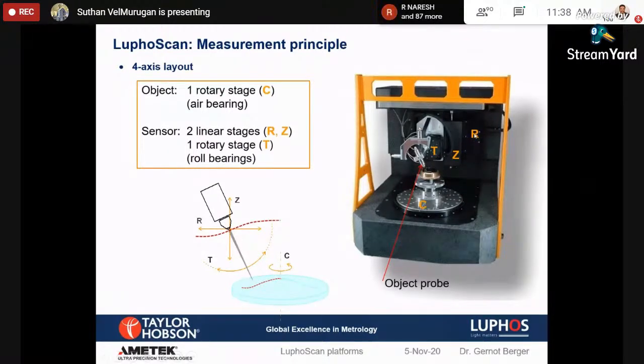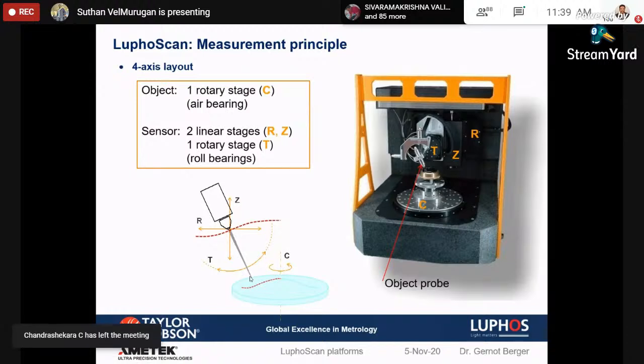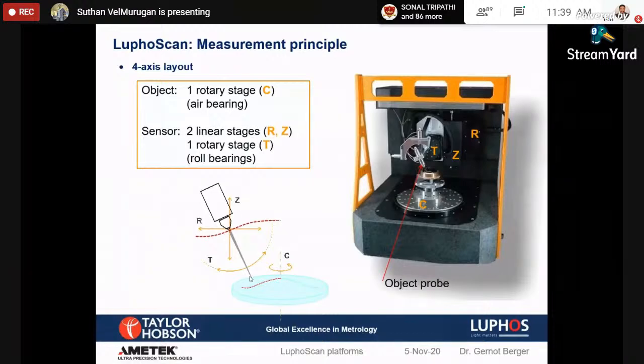The R is the arm axis, like an X-axis movement, and Z is the up and down movement. The T is the swiveling of the probe. The concept here is that the probe is always normal to the surface. You can see in the picture below that the laser beam is always normal to the surface. For example, with a concave shape, the contact point changes each and every time, and the probe tilts according to the radius of your sample.